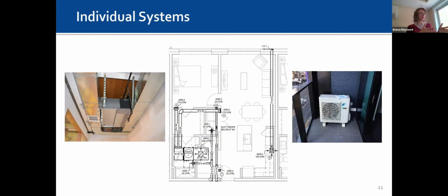So on the drawing here, you can see we dropped the bathroom, the closets, and the laundry area, and basically ran all the ducts there. The advantage is we stay below the assembly. We don't have any fire dampers, which is a cost savings. And because we've built this really tight envelope, and we've addressed air leakage, we're not feeling the need to run our ductwork to the perimeter. We've got a good piece of equipment that can achieve an appropriate air distribution so that we can get that air out across the room and get a nice airflow mix and distribution. And we're not having to compensate for leaky cold windows and walls because we were addressing that in other ways. So that's one of the real advantages of this.